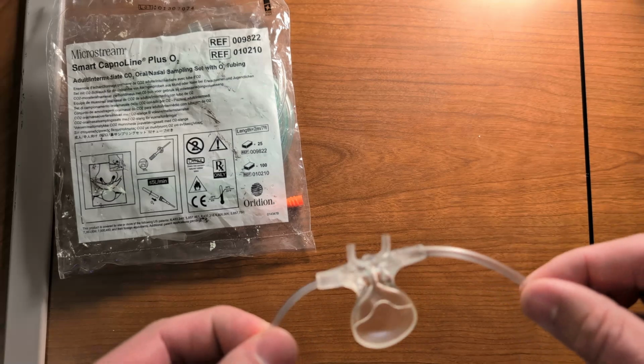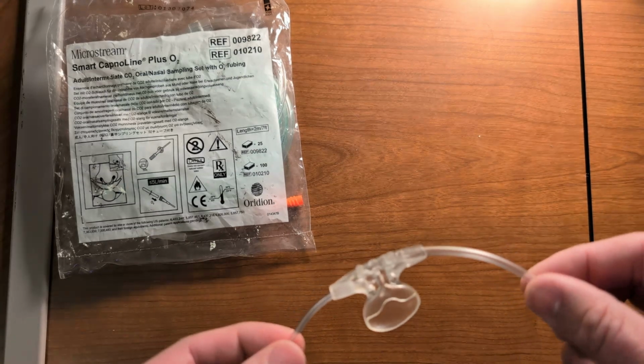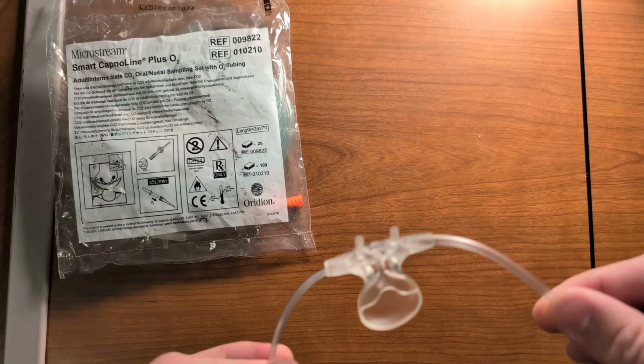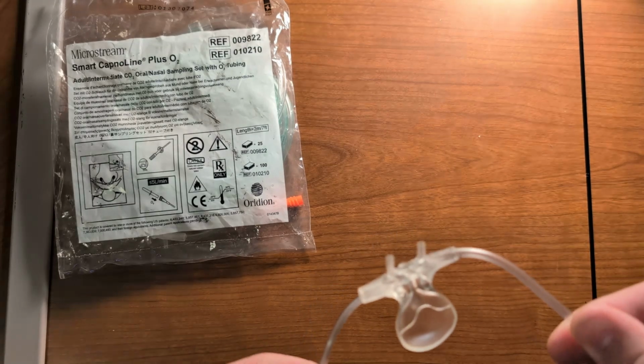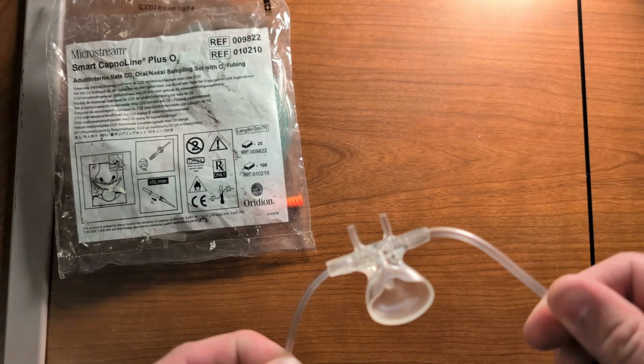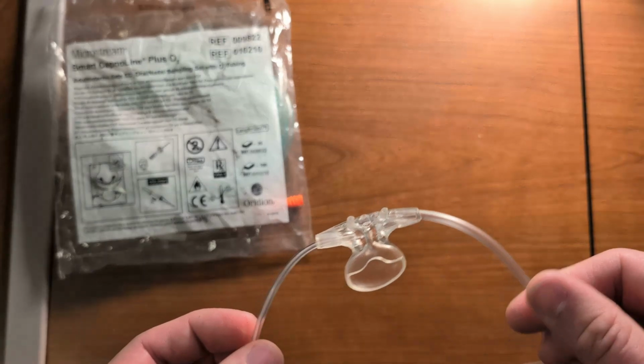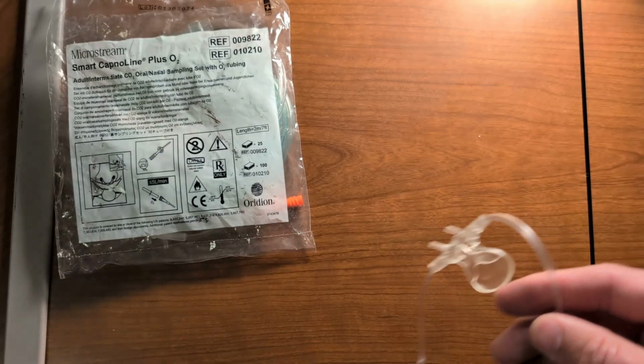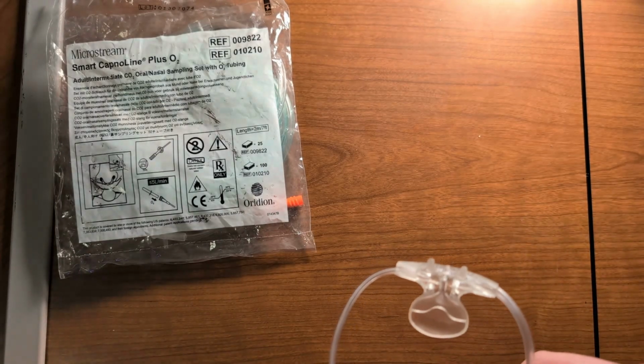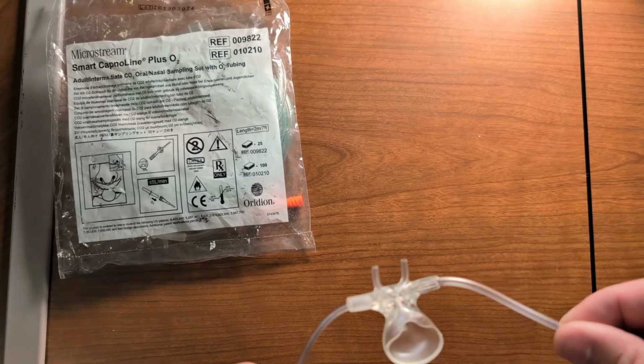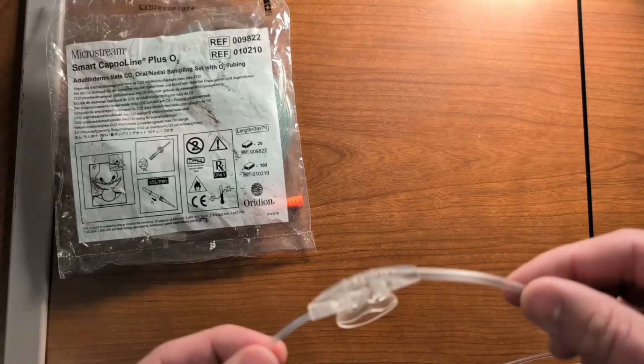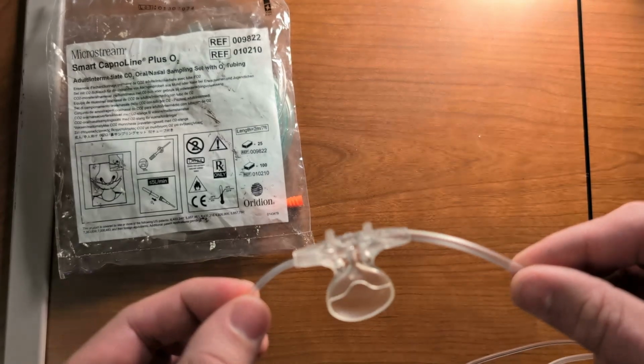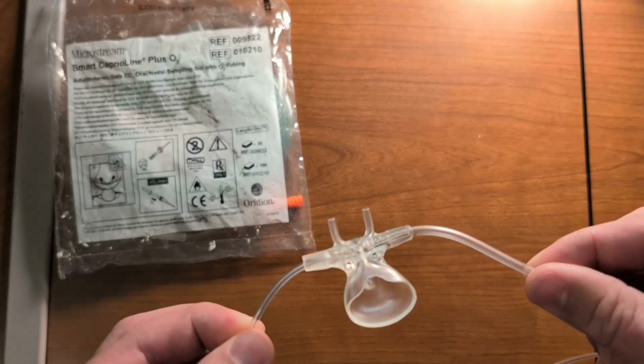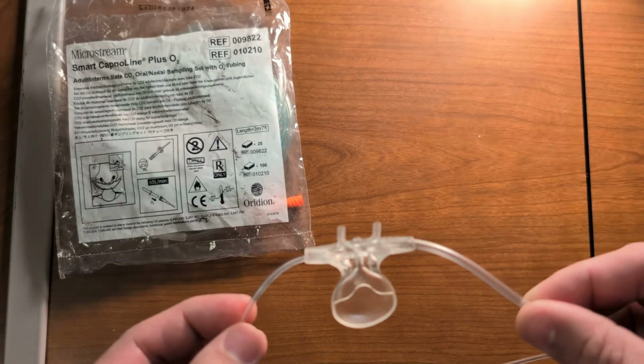I also tested this device underneath CPAP. Now with CPAP flowing, I started at 5 centimeters of PEEP, and I saw maybe a 1 to 2 millimeter drop in average end-tidal CO2 reading. As I increased that from 5 to 7.5 to 10 centimeters, I saw up to maybe a 5 millimeter drop in end-tidal CO2 reading. So you can use this underneath CPAP, but know that you're going to get a relatively significant drop in your end-tidal reading, and know to expect that.